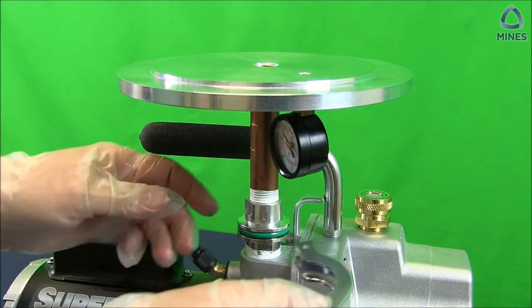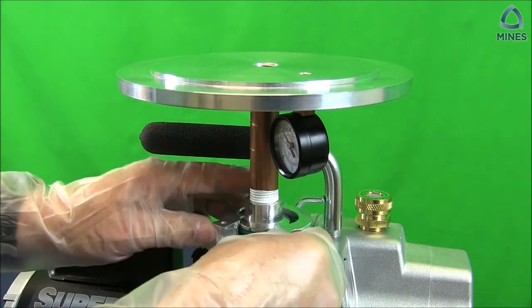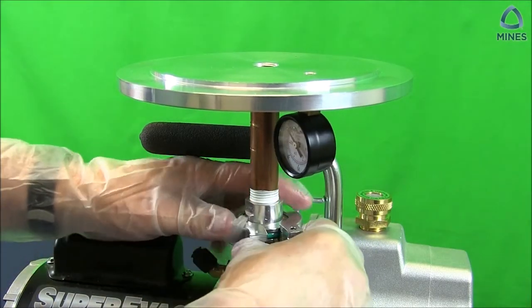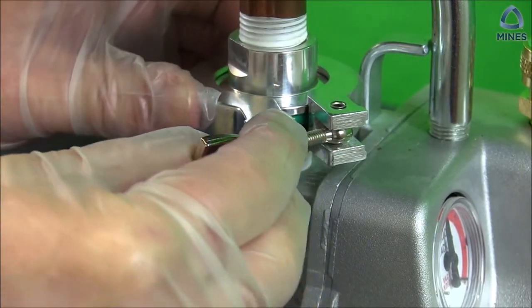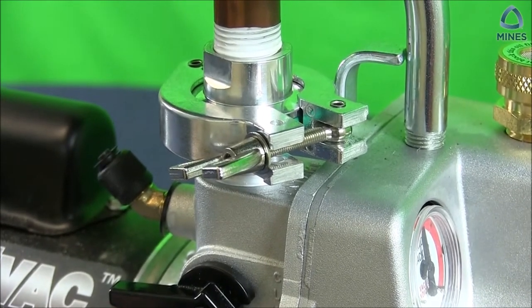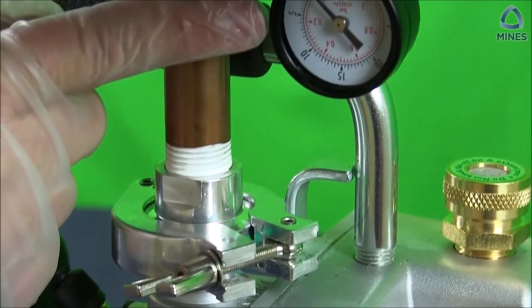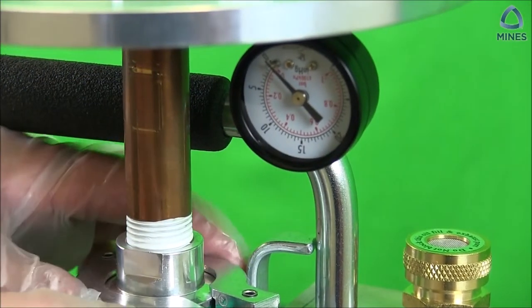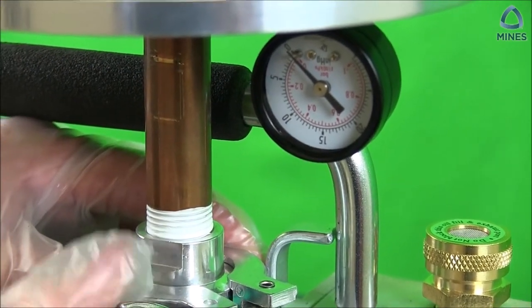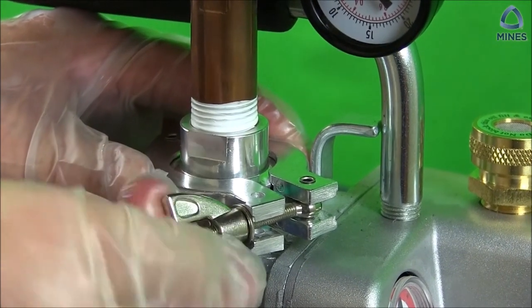Next, carefully position the NW clamp ring around the flanges and capture the flat washer on the wing nut into its clamping position. Be careful to assure that the washer is positioned between the wing nut and the captured clamping surface. Before tightening the flange, rotate the aluminum base plate so that the vacuum pressure gauge is easily read and does not interfere with loosening the vent valve. One typical position of the base plate is shown in Figure 10 of the assembly instructions.